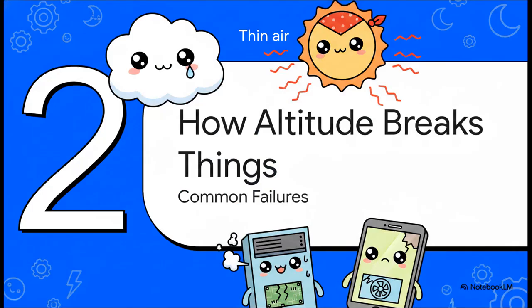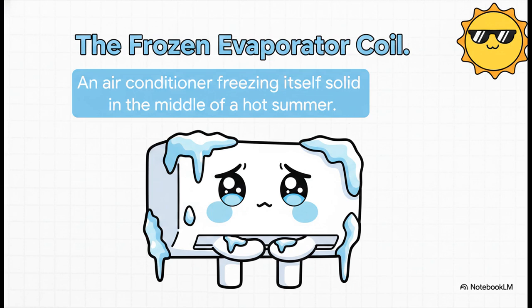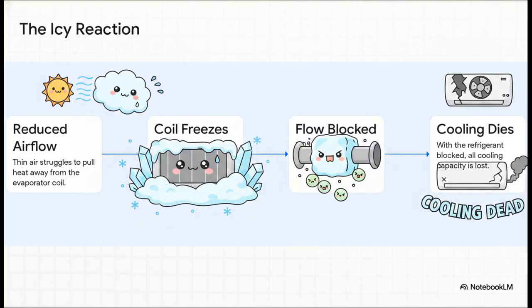So what does this relentless one-two punch of thin air and thermal stress actually do to these machines? Let's look at a couple of the most common ways these forces cause systems to give out. First up is something that sounds completely impossible, a real paradox of physics: your air conditioner freezing itself into a solid block of ice in the middle of summer. At high altitude, it's a constant threat. Here's how it happens: that thin, low-density air can't pull enough heat away from the system's evaporator coil, so the coil gets colder and colder until the condensation on it literally freezes into a block of ice. That ice then chokes off the refrigerant flow, and just like that, your cooling is gone.